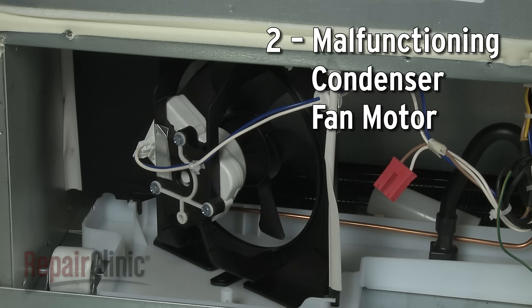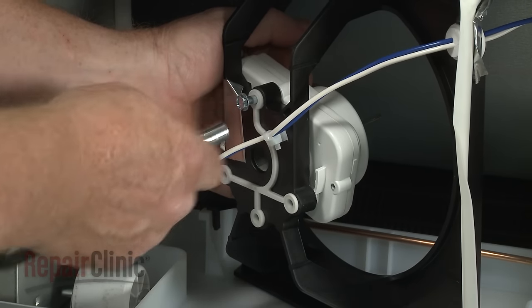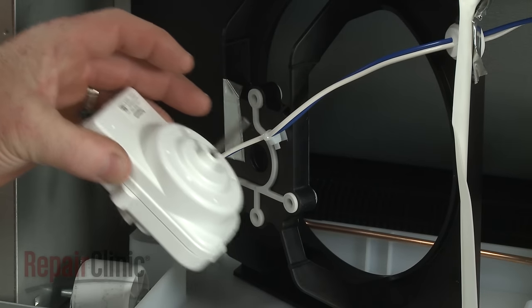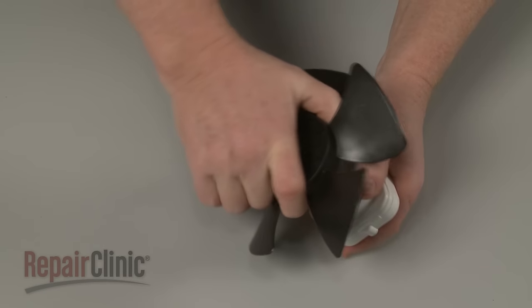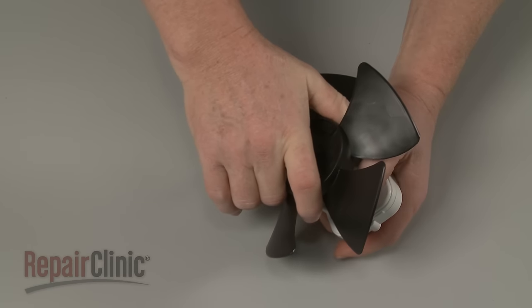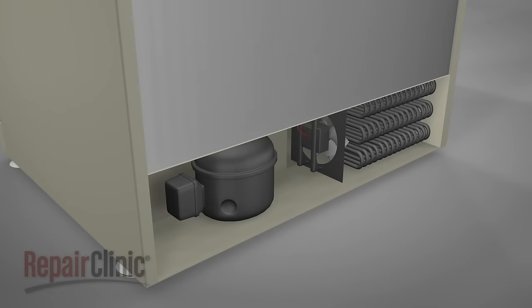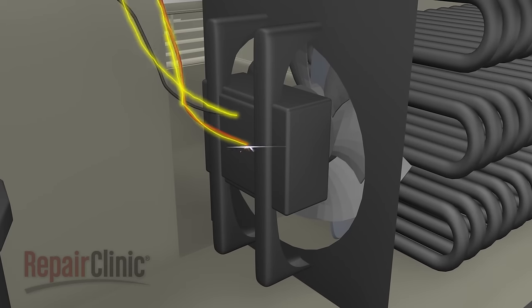A malfunctioning condenser fan motor could also prevent the refrigerator from cooling properly by failing to draw air past the condenser coils. The component can fail mechanically or electrically. A broken fan blade or a blade that does not turn freely could indicate a mechanical failure. If the motor is receiving power but doesn't run, then the motor has probably failed electrically.